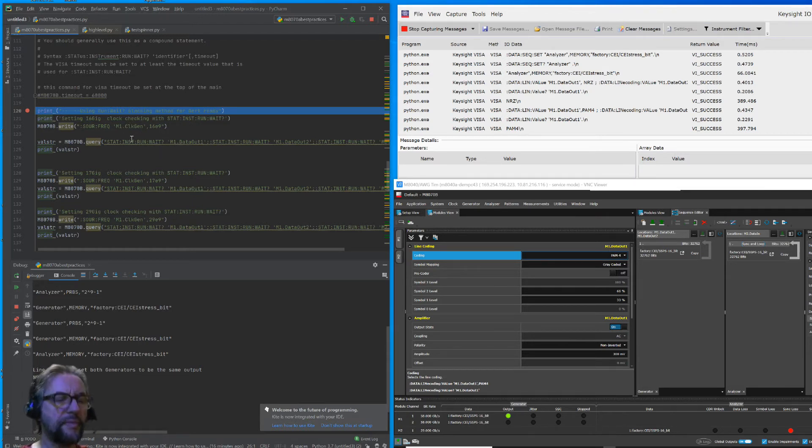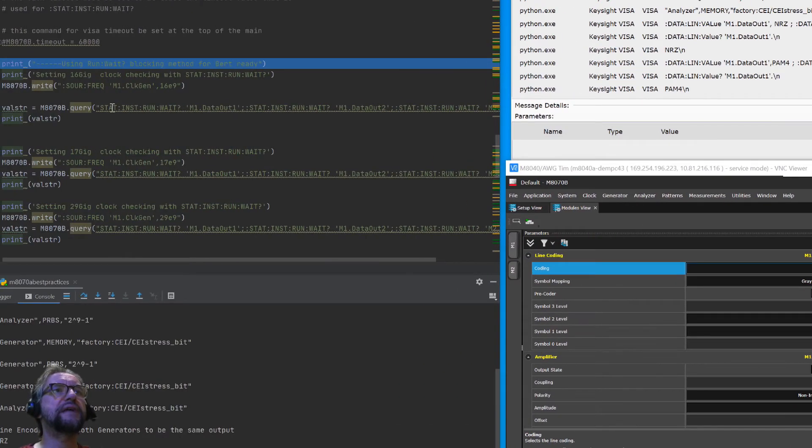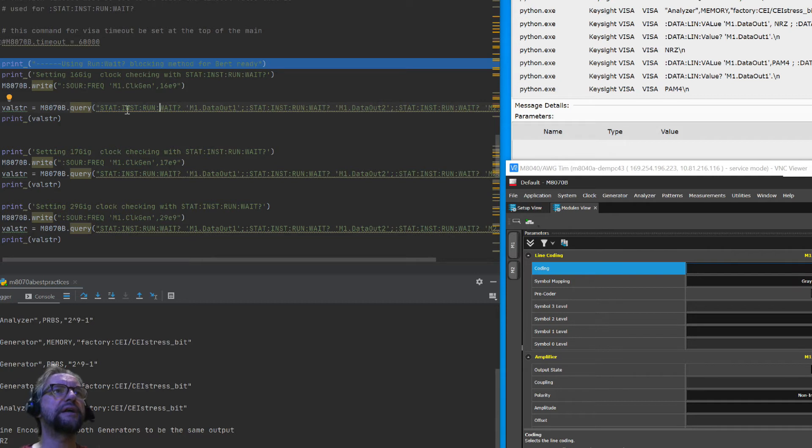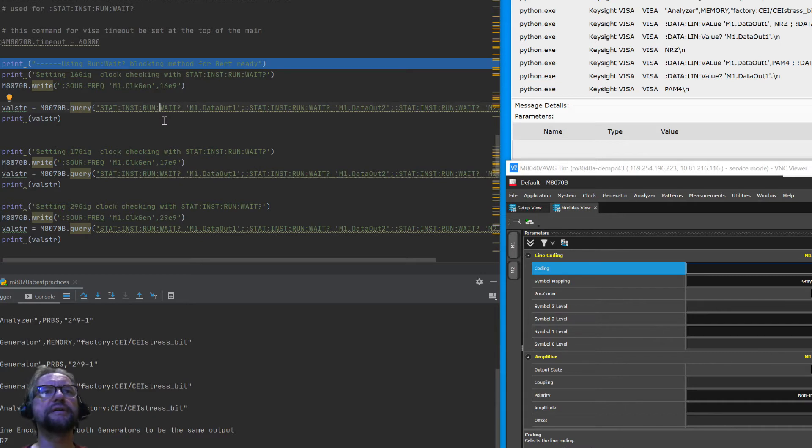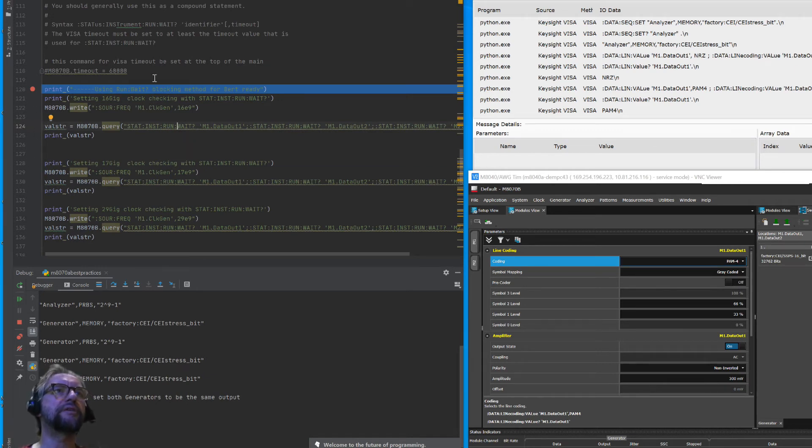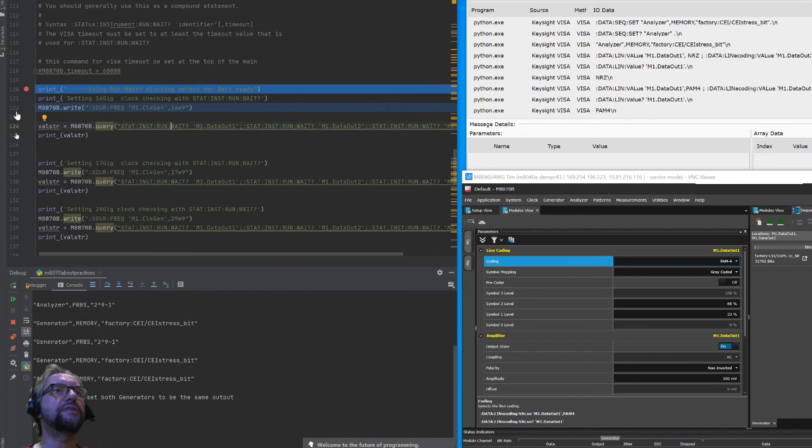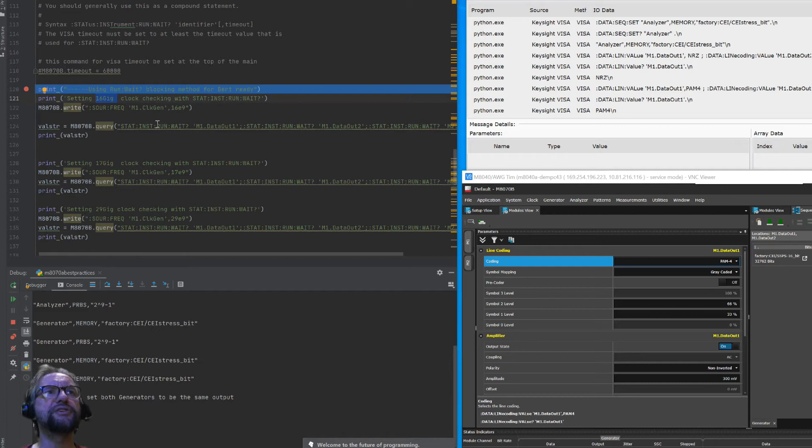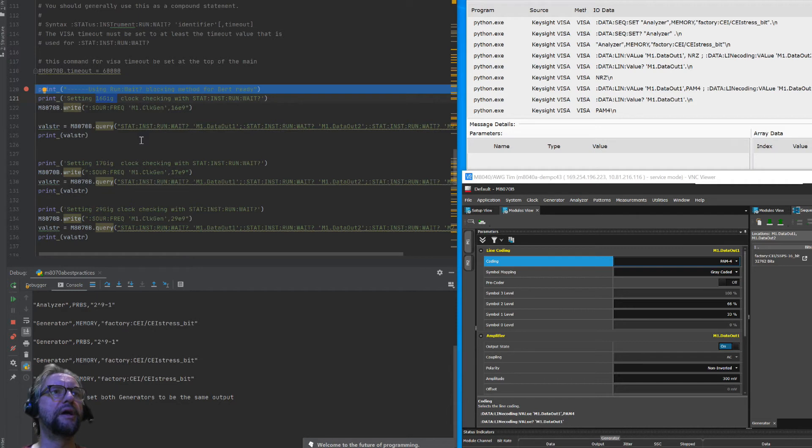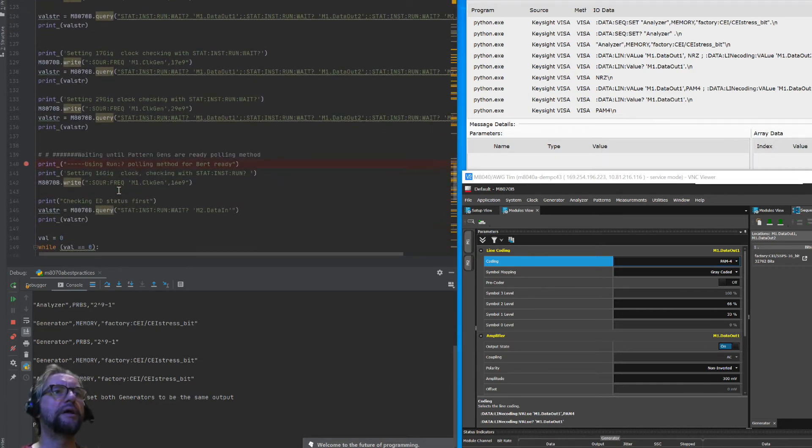There's a command called, there's a blocking command called stat inst run wait. There's a blocking version. And I'll show you right after the non-blocking version where you have to do polling, stat inst run and then query question mark. So I'll show both examples. But what I'll do when I run this is I'm going to, it's kind of doesn't really demonstrate this properly unless I, I'm in stop mode right now running through. So I've got, actually what's going to happen is it's going to execute three different writes to the clock setting. So 16 gig, when I write to that, it's going to take a number of seconds to complete that operation. If we just started issuing these one after another, we would run into problems. Now, because we're doing the run wait, it's going to, the blocking statements will work no problem. But we should not issue any more commands. And this is how I've written the code is wait for this to come back and then move forward.